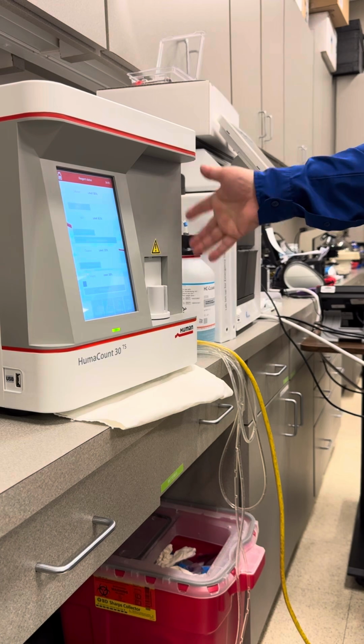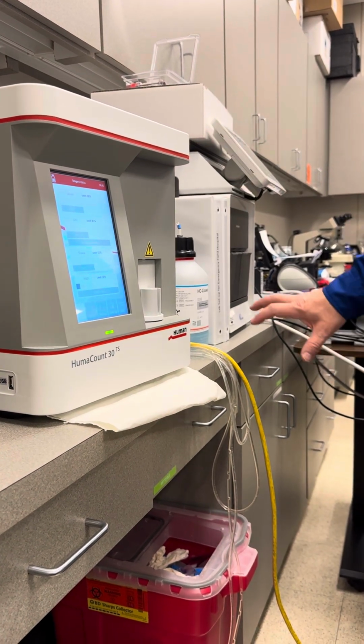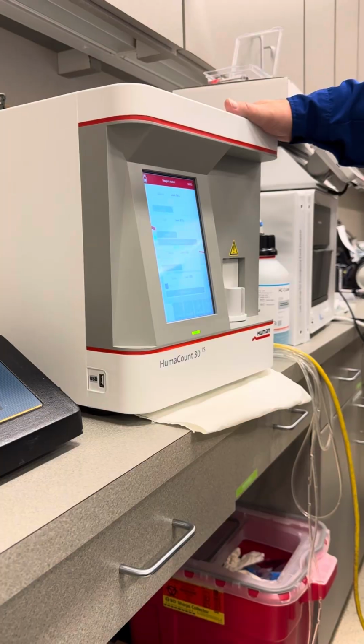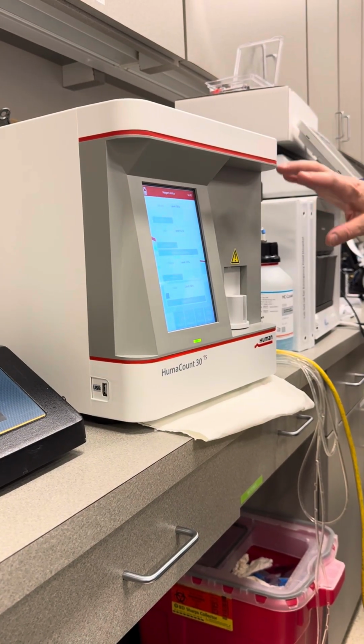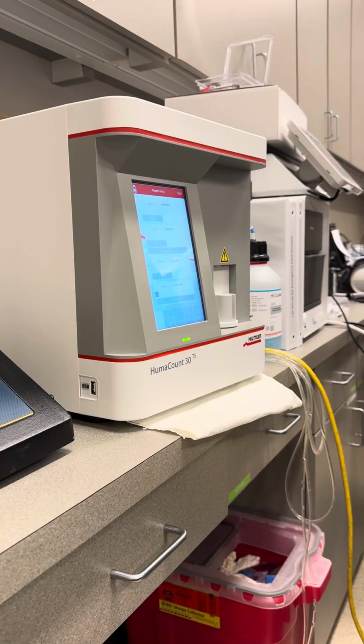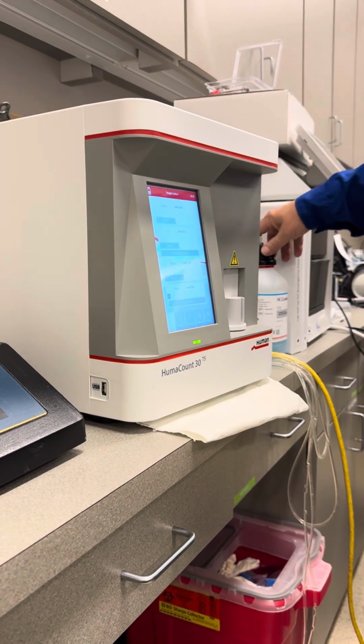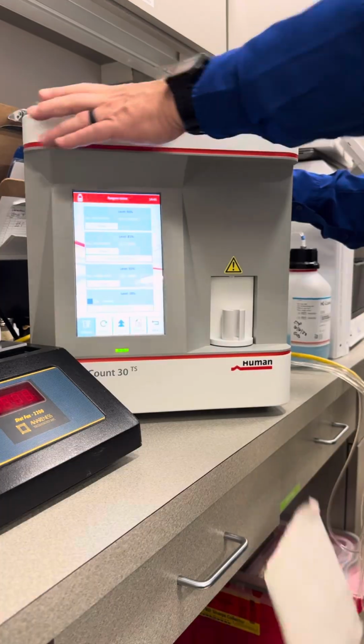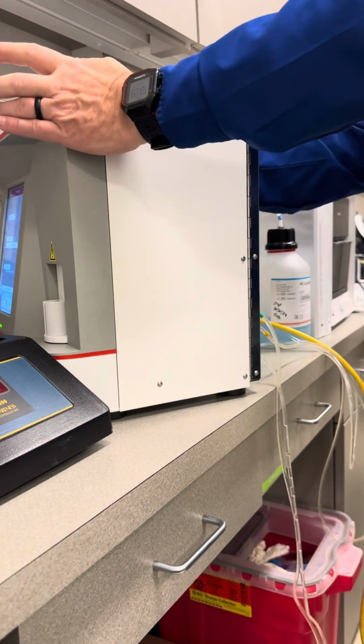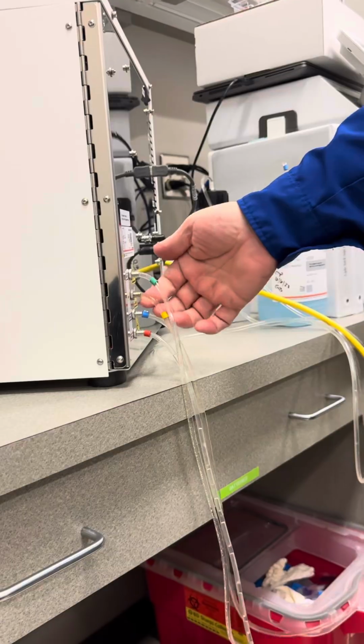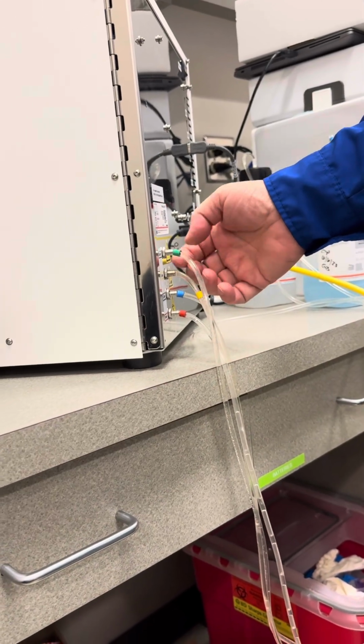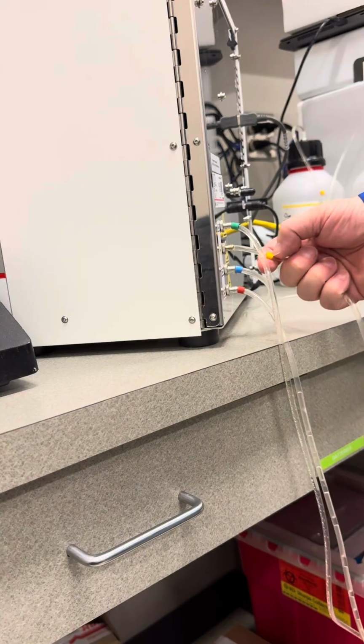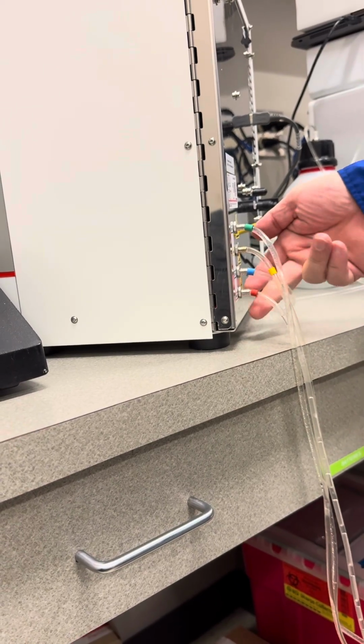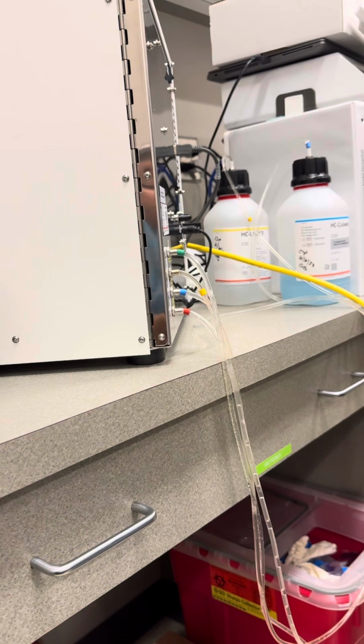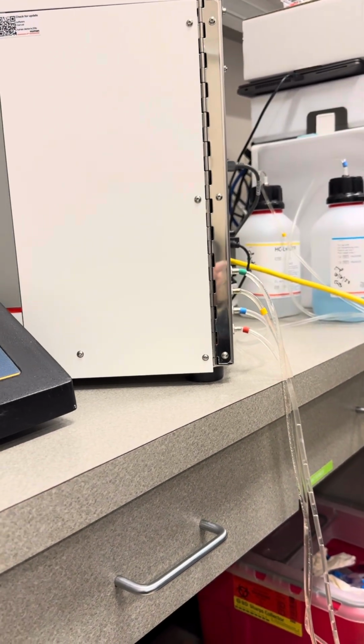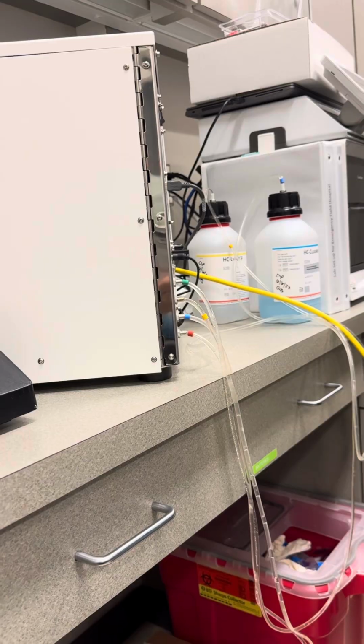For some reason, if you've been working on it, or if you had shut it all the way down to where you're going to transport it somewhere else, then you can reprime them all at one time. As far as your reagents, they're all color-coded onto the back of the instrument when you're hooking it up. So green goes to green for your diluent, yellow for lyse, your cleaner is going to be blue, and then your waste is red. That's pretty med-tech proof. Yeah, it's fairly simple as far as that goes.